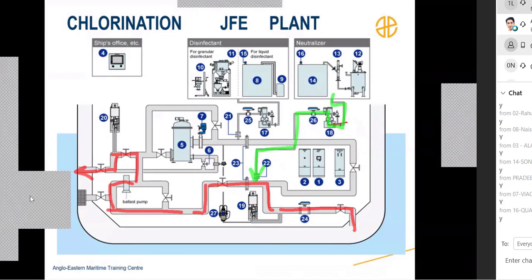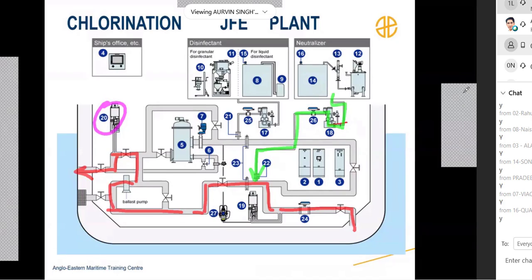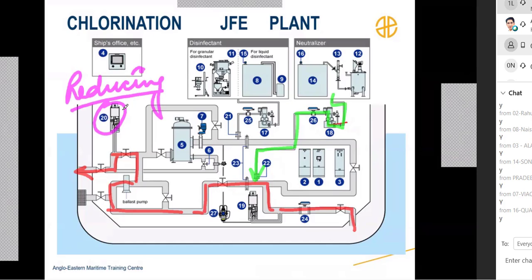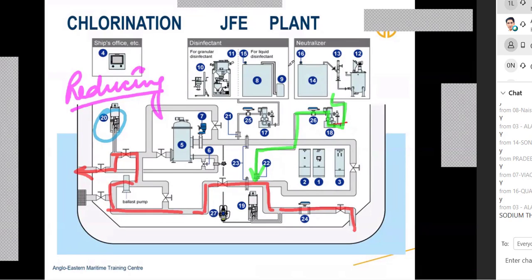So this is the feedback from the sensor. You are modulating or changing the flow rate of the neutralizing chemical. And what neutralizing chemical is used normally? So first of all, if it is an oxidant which you are neutralizing, you must be using some kind of reducing agent, because an oxidizing agent can be killed by a reducing agent. Okay, so usually you are using sodium thiosulfate as a neutralizing agent. Yes, that's right. So you are using this chemical here, sodium thiosulfate, and it is being dosed into the water.